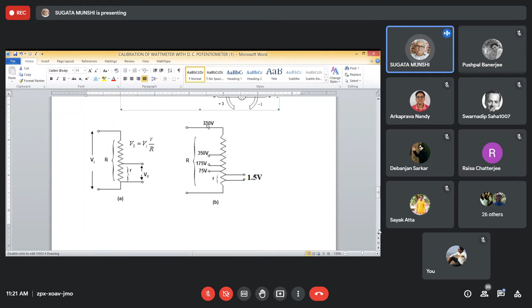Here is a realistic drawing of the voltage ratio box. There are several tappings on the input side, meaning that when you connect a voltage source between the two extreme points, if the maximum possible voltage value is 750 volts, then across the output terminals you get a value of 1.5 volts. That means across the two extreme terminals you cannot apply a voltage greater than 750 volts. That is the first point. Secondly, if the voltage is less than or equal to 750 volts, it will be scaled down in this ratio, 750 is to 1.5 volt. So you can easily understand what the voltage value will be if it is around 600 volts: 1.5 by 750 into 600. But these are the conventional tapping voltages.